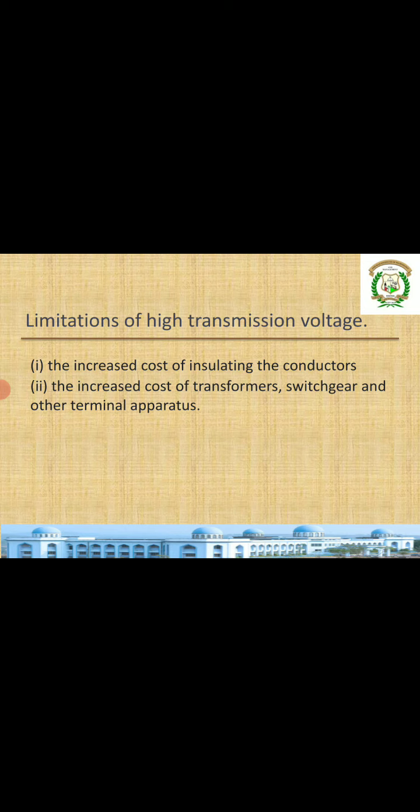The second limitation is the increased cost of transformers, switchgear, and other apparatus. The cost of transformers depends on the voltage range because they require their own insulators, conductors, and larger physical size at higher voltages. Switchgear and other equipment costs also depend on voltage level. Since we can't simply go for high or low voltage, we need to make an economic choice of voltage level that achieves reliable operation with minimum overall cost.